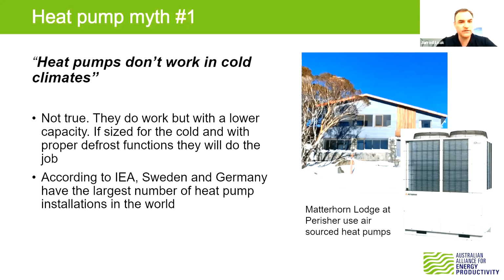The first one we hear probably most often is that heat pumps don't work in cold climates. This is certainly not the case. They do get lower performance compared to when the ambient air is warmer, with an air sourced heat pump, but they still do work. You do need to size them for that colder weather, because they still work even below 0 degrees.